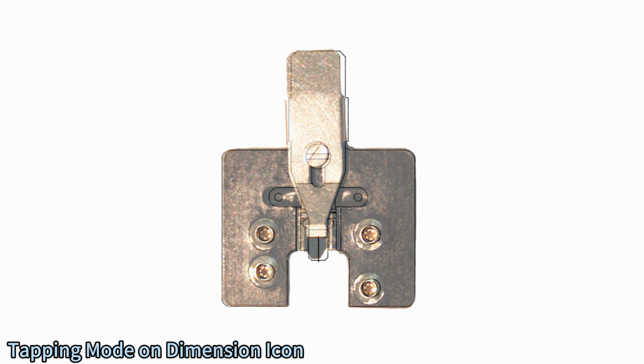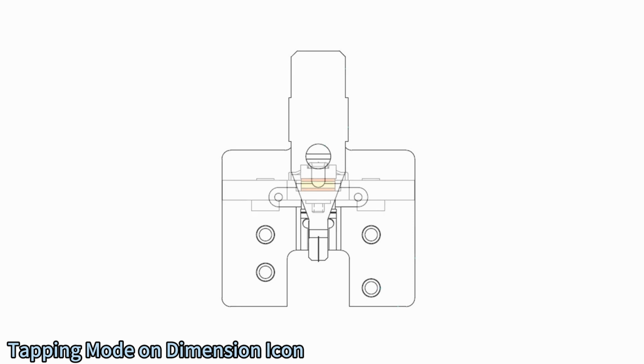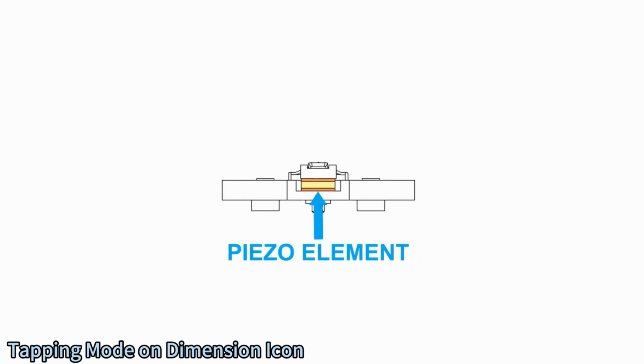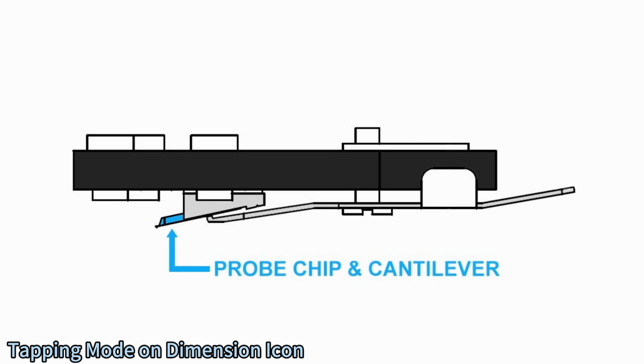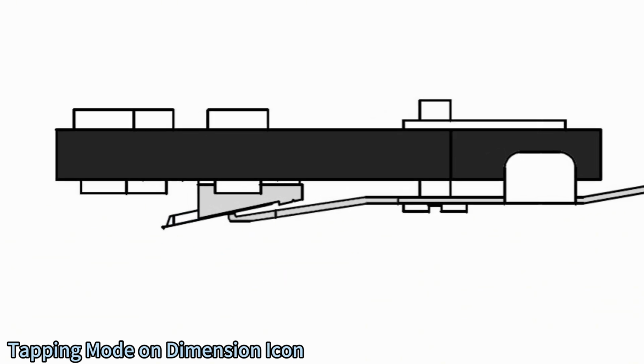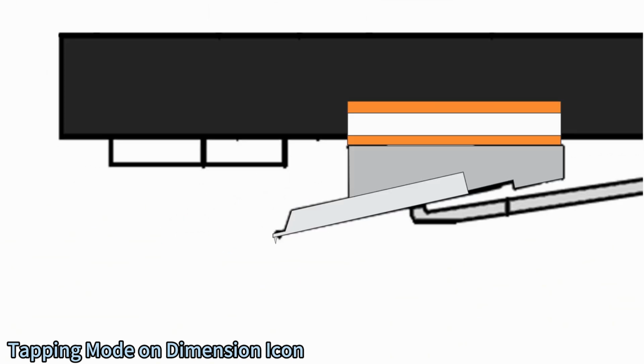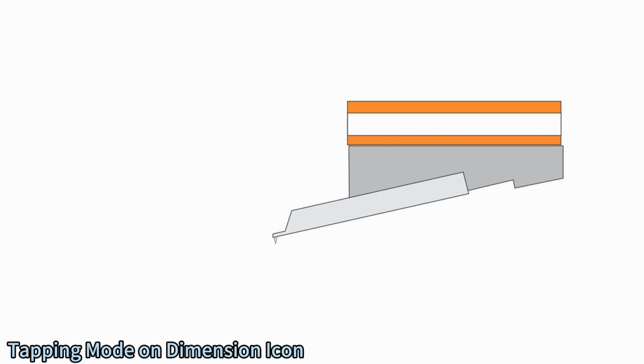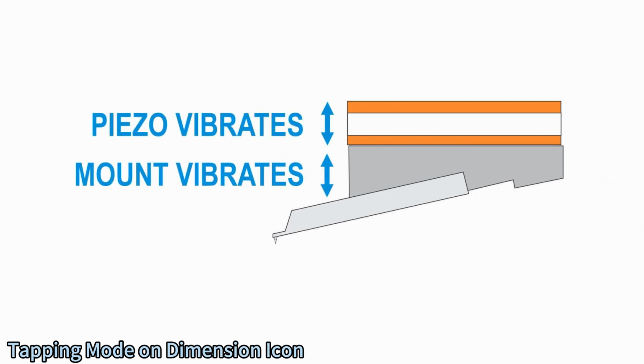The probe holder contains an embedded piezo layer under the chip mount that vibrates at a frequency generated by a signal from the controller. The vibrating piezo induces the vertical motion of the probe cantilever that ultimately results in a maximum vertical displacement, or resonance.